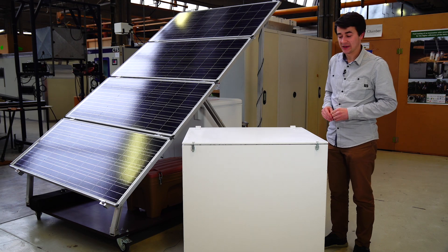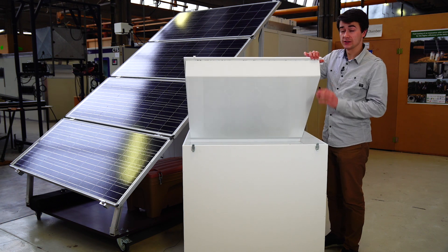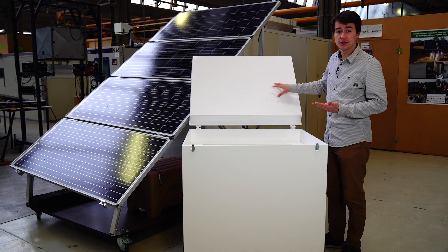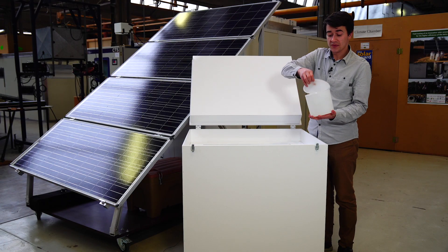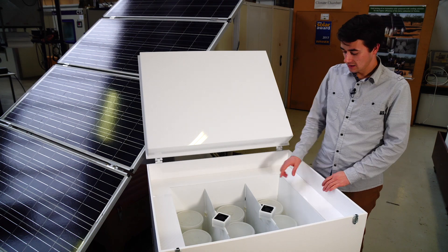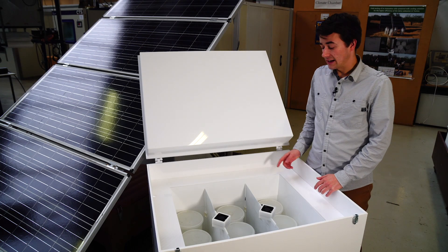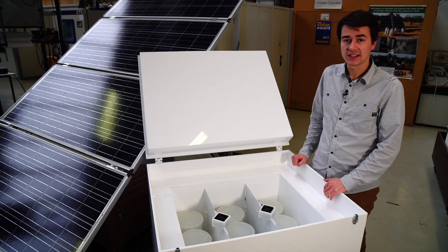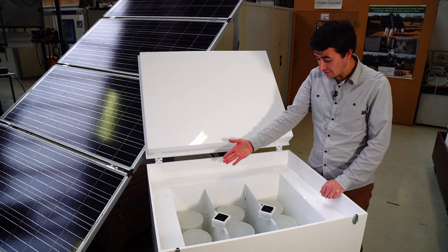This is our self-made solar powered ice maker. The construction was done in three parts: the outer box is made of painted wood, the insulation material is polystyrene covered with a plastic layer for waterproofing. With this ice maker we can produce two-kilogram ice blocks. Two evaporator plates divide the freezing room into three chambers, with fins at the top of the evaporator plates for better heat transfer. At sunny conditions, only the middle chamber is used for daily ice production, yielding around 18 kilograms of ice per day. For autonomy during cloudy conditions, ice from the left and right chambers can also be used.